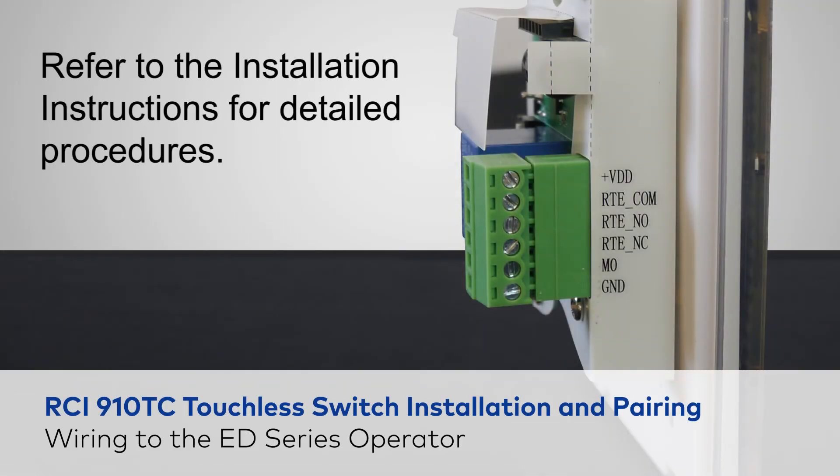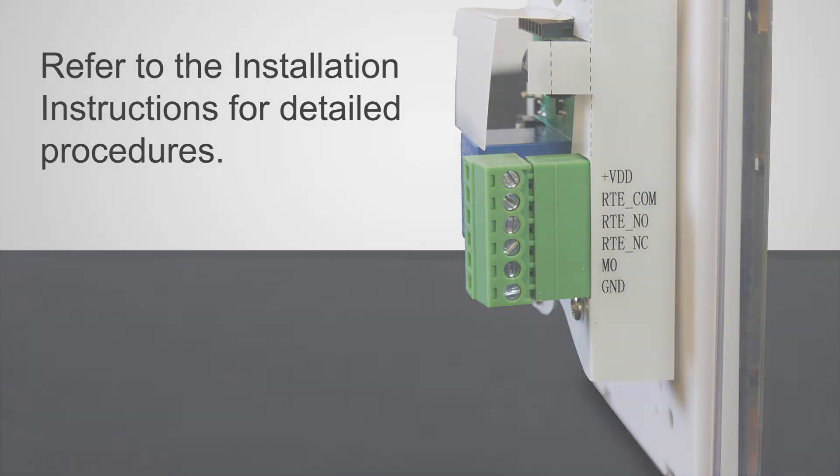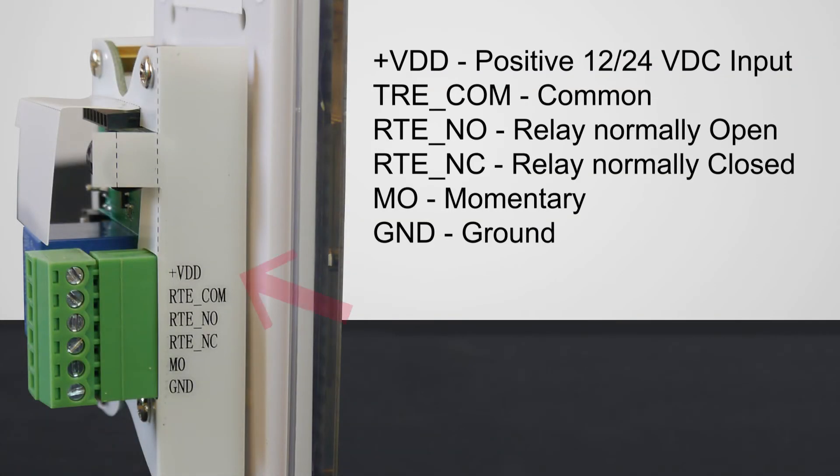Before you wire the 910TC touchless switch, let's first review the terminals. There is a positive 12 to 24 volts DC input, common, relay normally open, relay normally closed, a momentary button which is used for a request to exit device, and a ground terminal.